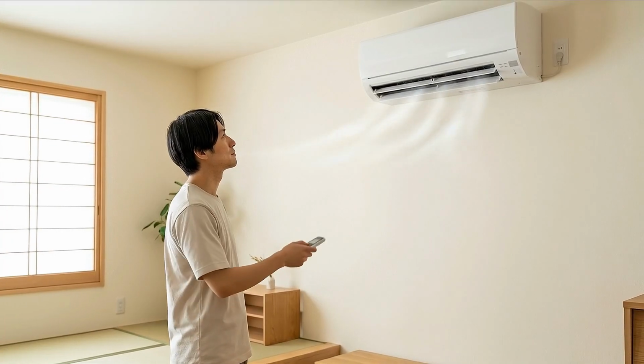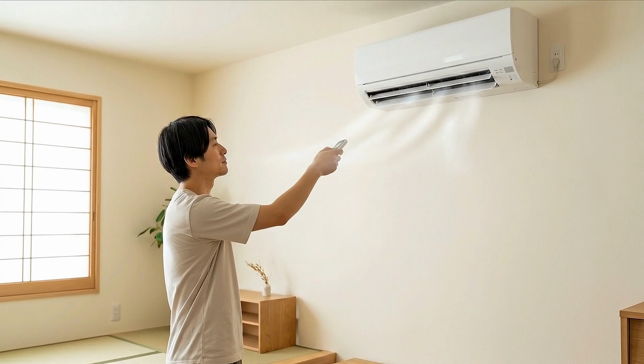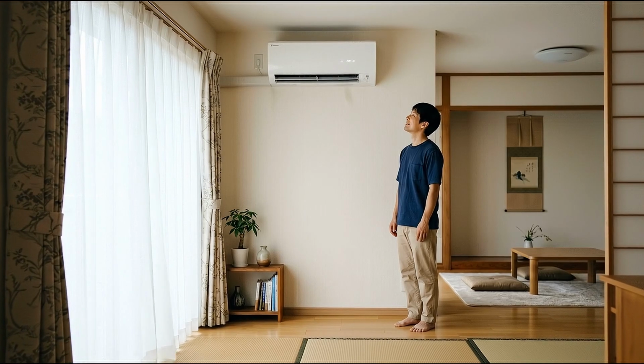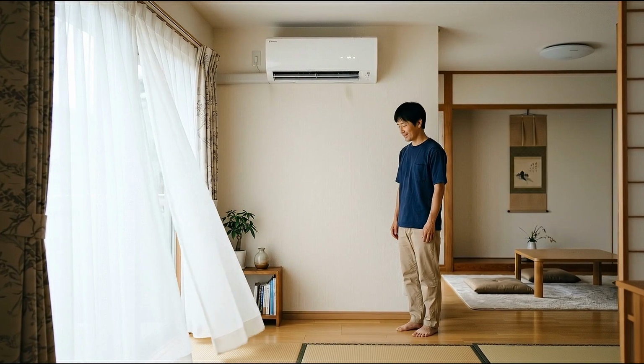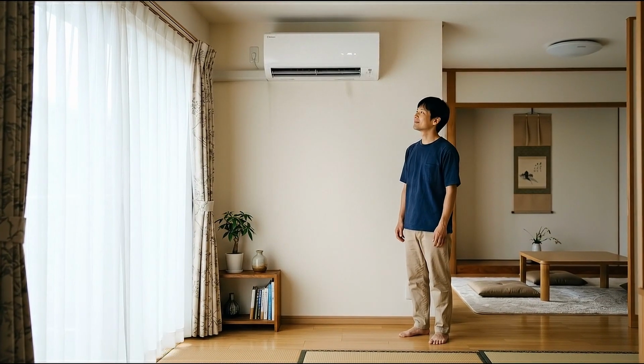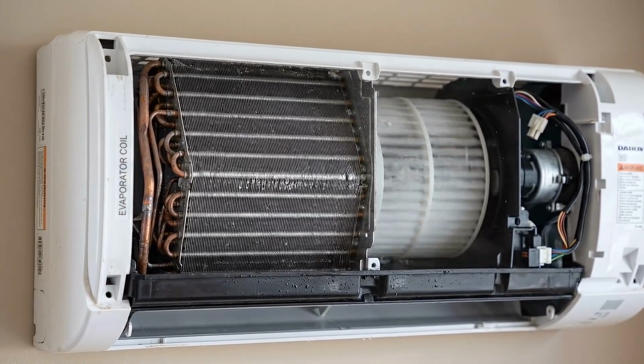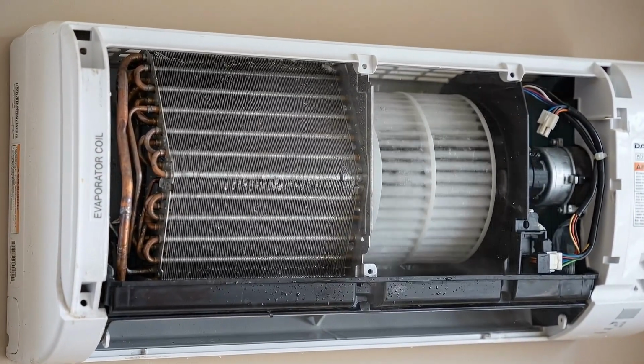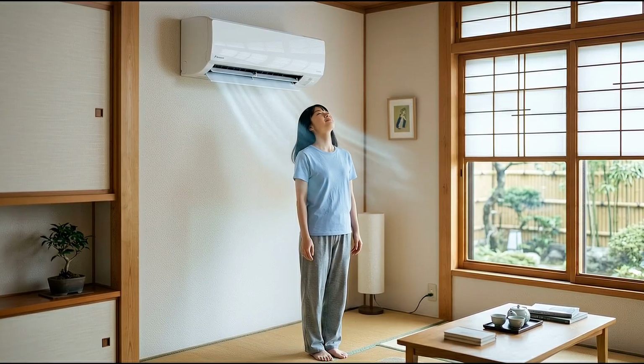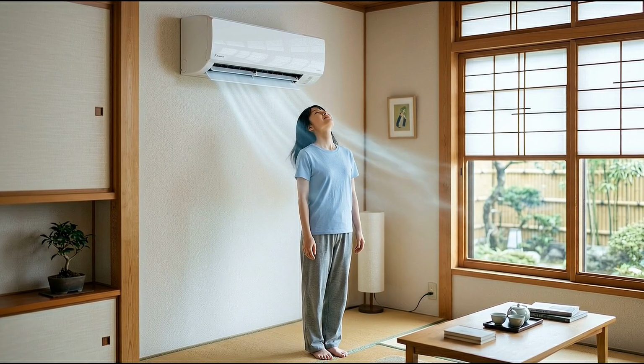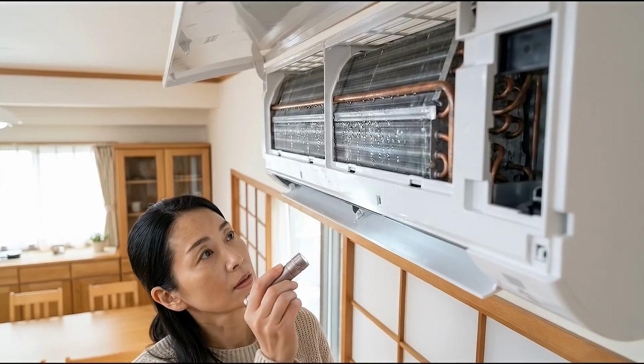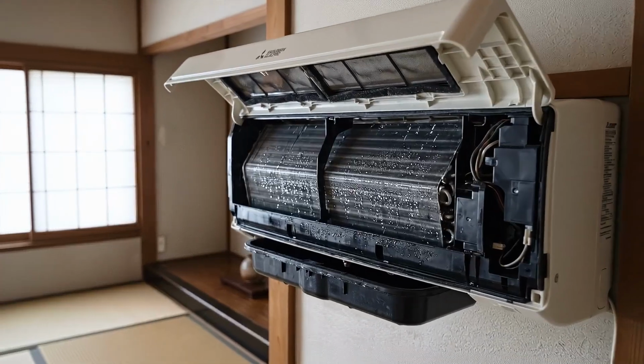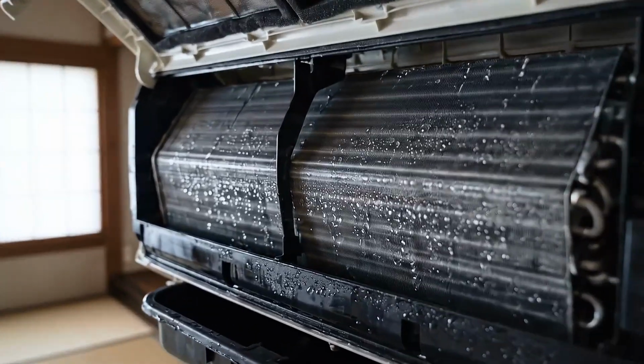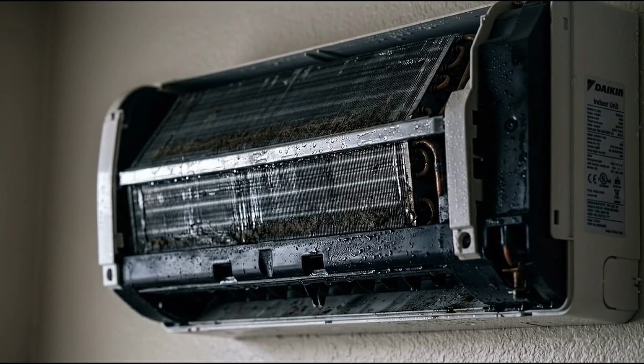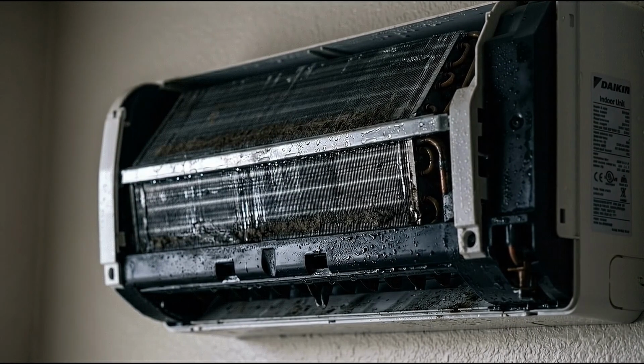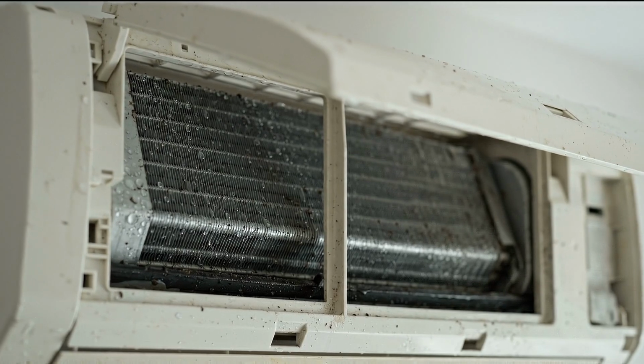When you turn off the cooling, the system automatically switches to fan-only mode and runs for 30 to 90 minutes, sometimes up to 2 hours on certain models. The purpose is simple. It dries the evaporator coil and the interior surfaces of the unit after every cooling session. Why does that matter? Because when your air conditioner cools the air, moisture from the room condenses on the cold evaporator coil. When you shut the unit off, that moisture just sits there in the dark. Mold spores are already in the air. Give them a wet surface in a dark enclosure, and colonies start forming within days.